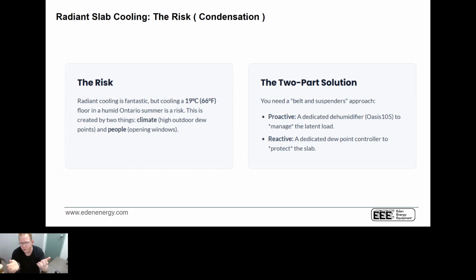If you're going to do a two-part solution, you need to look at it as a belts and suspenders approach. You need a proactive and a reactive solution to what happens if I'm doing radiant cooling. Number one is, how do I make sure it's going to work if I'm using a slab? And number two, how do I overcome the human element, i.e. the unintended consequences of putting in a system? You've got everything working the way it should, and then somebody throws a monkey wrench in, like leaves all the windows open. You never figured, why would you cool the home and leave all the windows open?